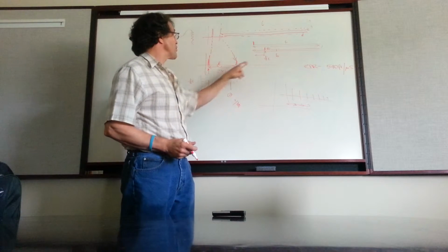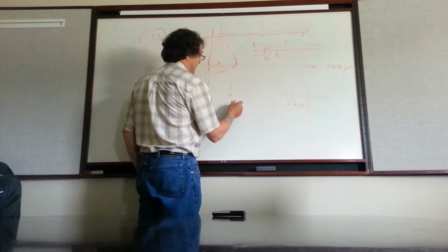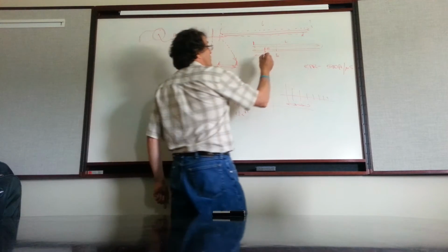By the time you saw it here, it's already travelled. So when you see this pulse, you've ignored this time because you didn't know it was there, which also means you've ignored that time too, because that occurred as well. So I've got to subtract off here a quarter L. Now I'm left with 1.5 L. Well, we know that the fault was 3/4 L, wasn't it? This is the actual fault distance from the tail.